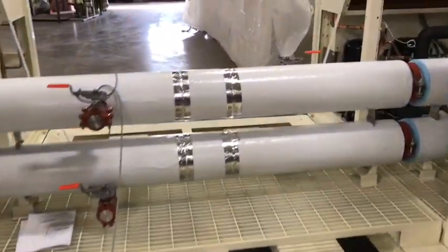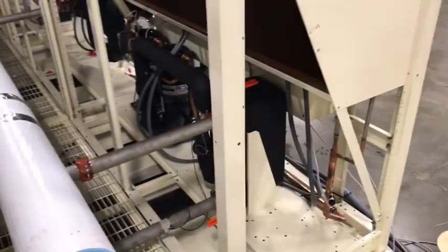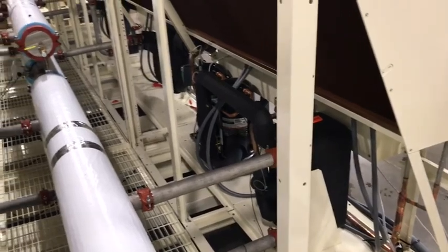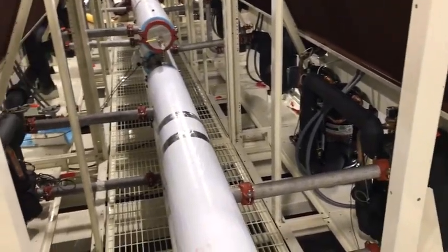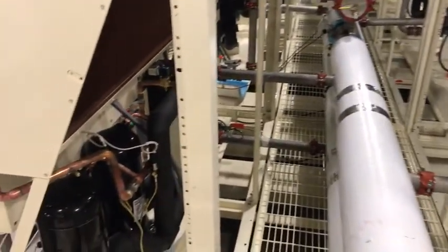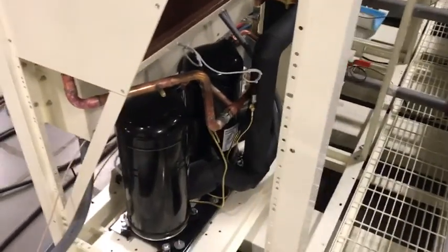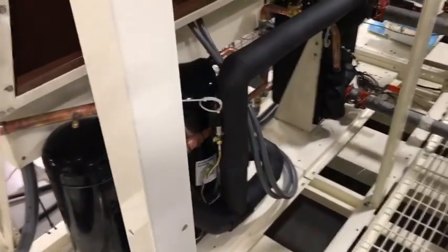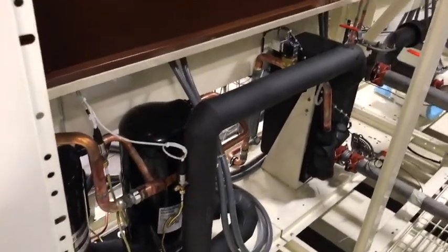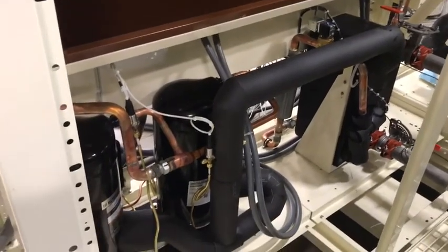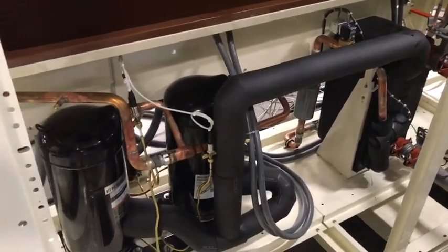So now we'll work our way into the break in this array and look back down, seeing free cooling modules on the right, 3 of them, and then 2 free cooling modules at the far end, and the master mechanical module here with its evaporator, dual circuited evaporator, and 2 tandem compressors.